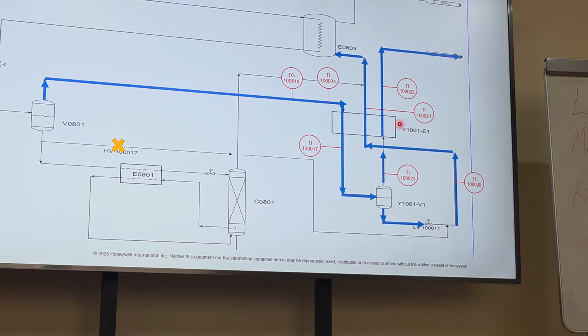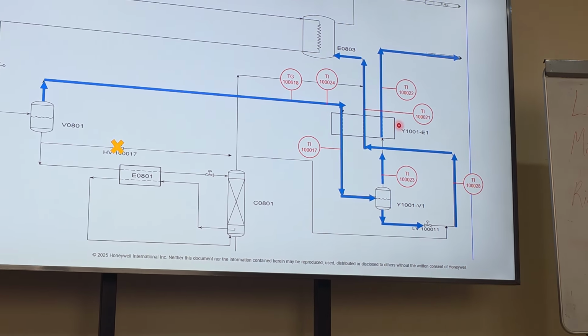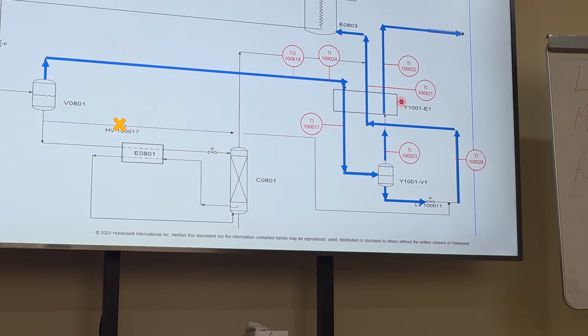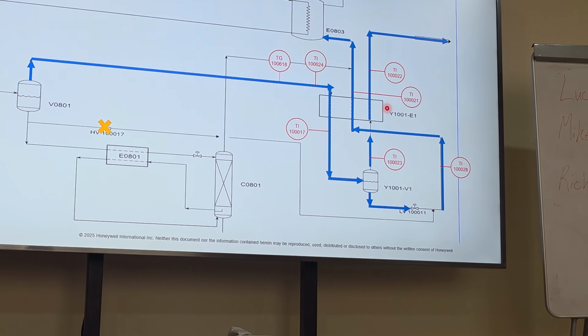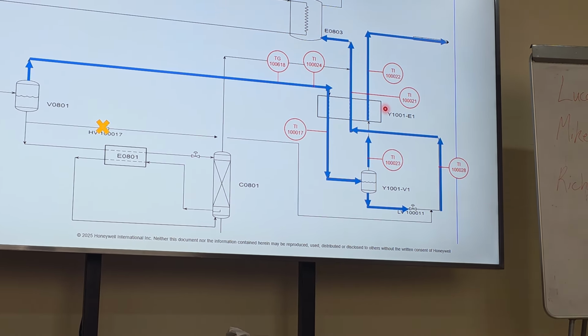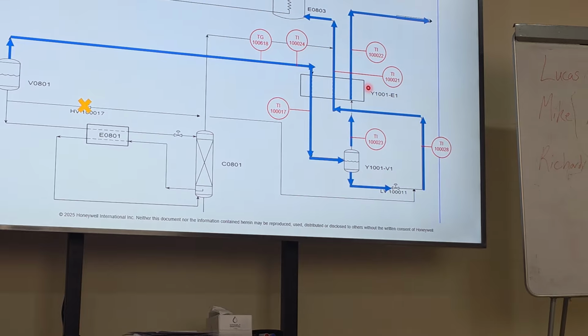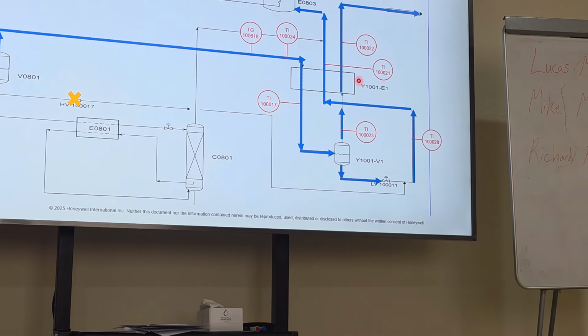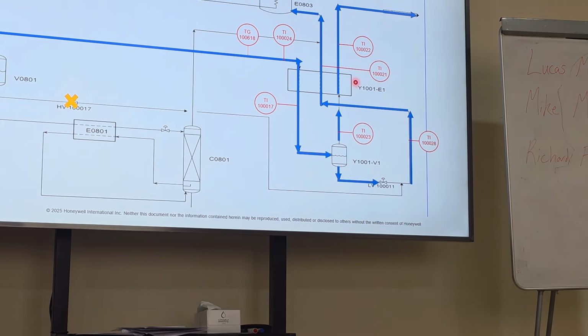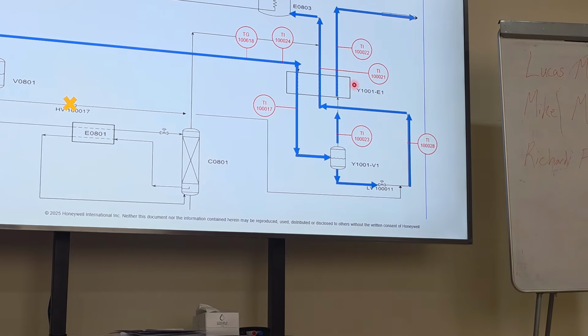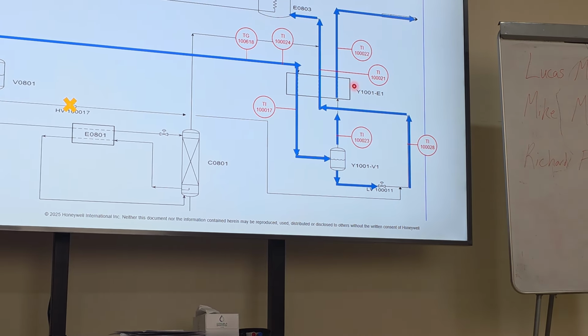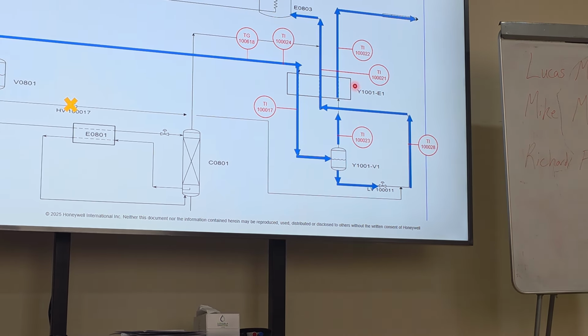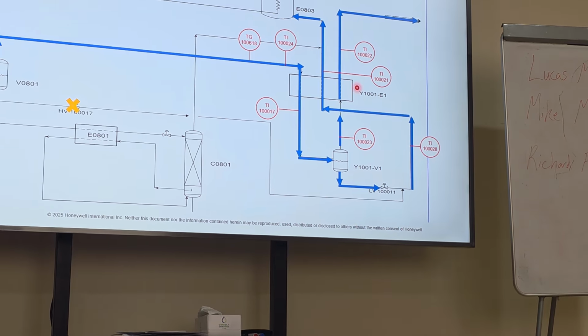This is probably the easier way of doing it, in my opinion. And I'm sure for those of you with the old unit 10s, it's probably easier to do it this way, and I think you have to, right? Because the brazed aluminum heat exchanger has a helium recovery pass for the flash gas. Correct. So you have to, pretty much. So, same idea then. It's just that now the flows are slightly different paths.